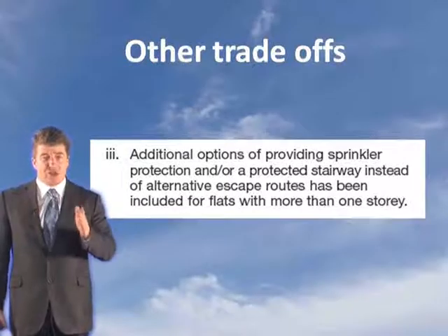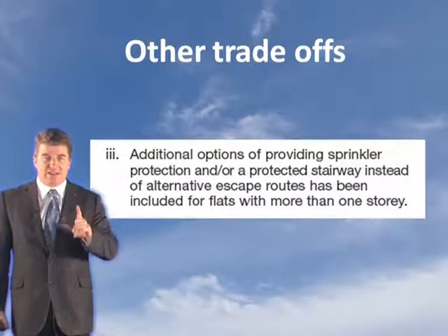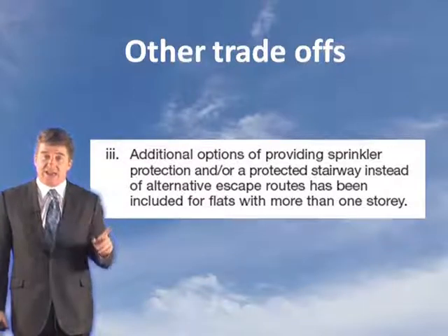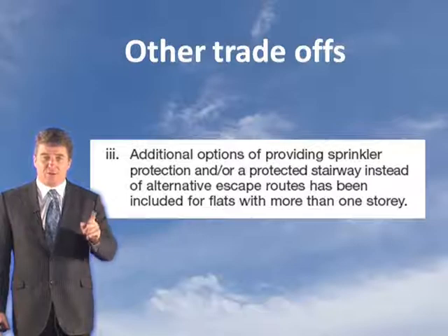Again, additional options of providing sprinkler protection and/or a protected stairway instead of an alternative escape route have been included for flats with more than one storey. So flats with more than one storey, you put a sprinkler system in or a protected stairway instead of having an alternative escape route. So again, that's another benefit of putting sprinklers in.